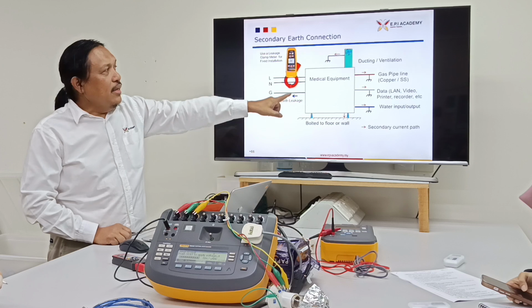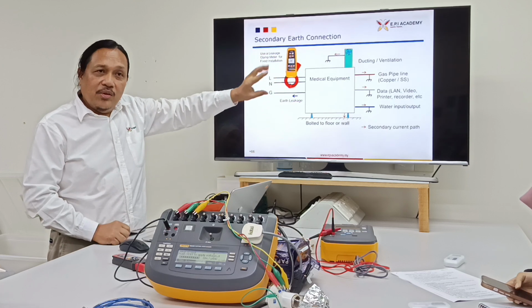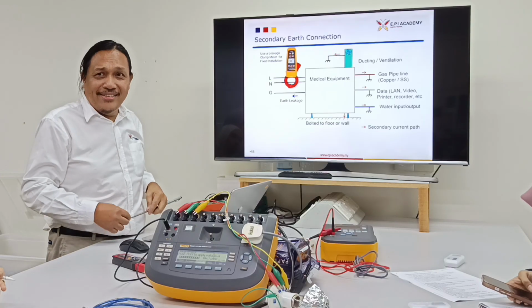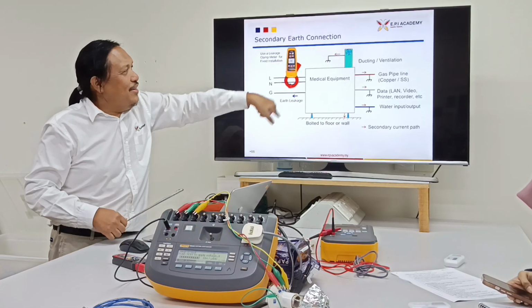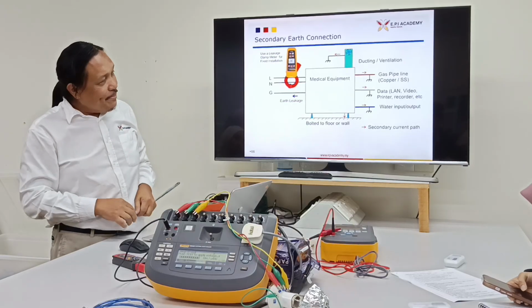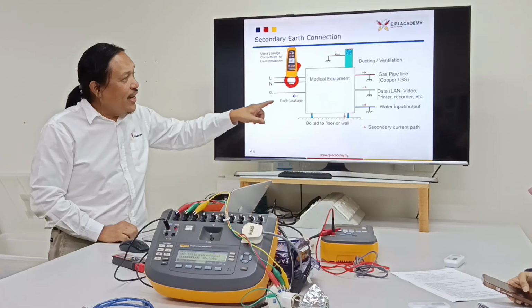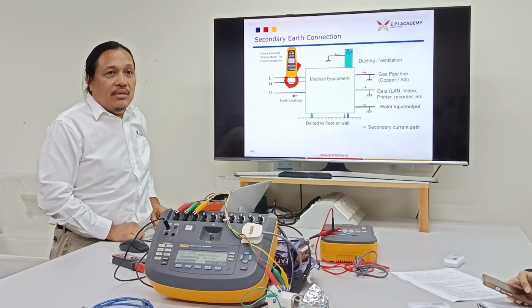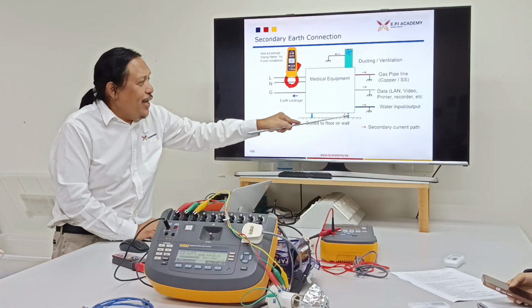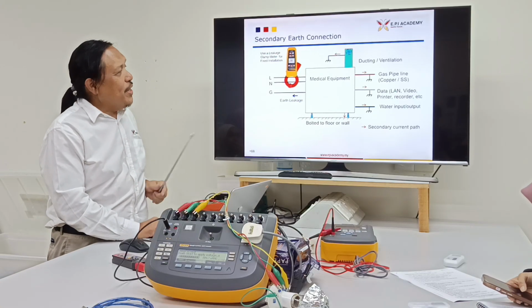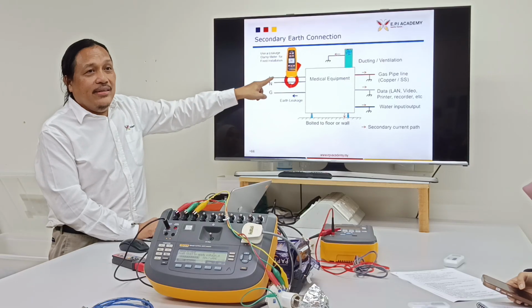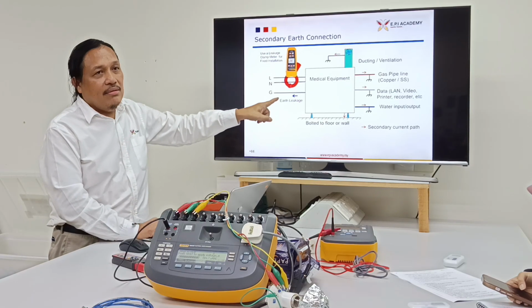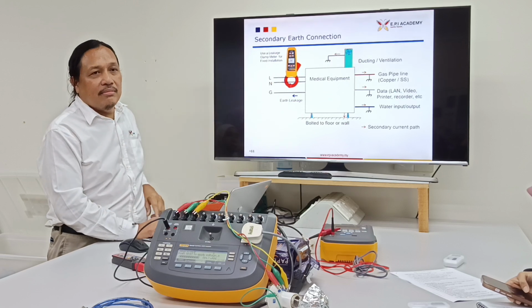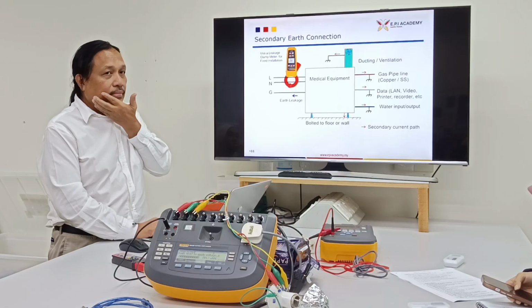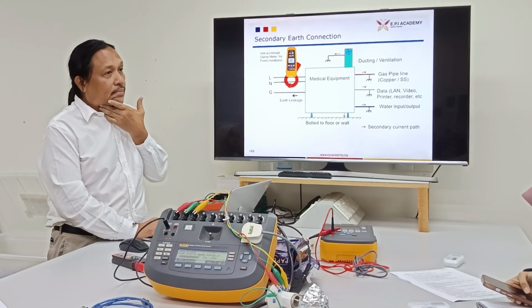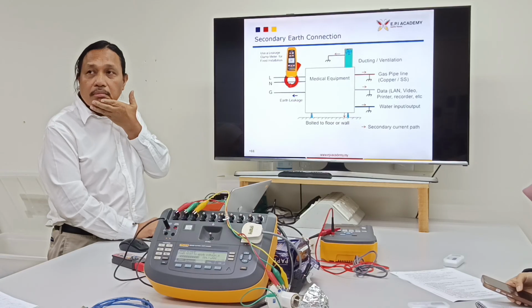So how do you measure the leakage? Use the differential method. Use the clamp meter method. This is called the differential method, right? Yes. That's why I put the photo of the clamp. Differential method, because you cannot measure this leakage. How do you put a clamp meter there? That's not possible. So just subtract the current here. Subtract. Dia baru nak explain. So you will get all the leakage minus the leakage. Lepas tu total leakage tolak dengan ground punya leakage.